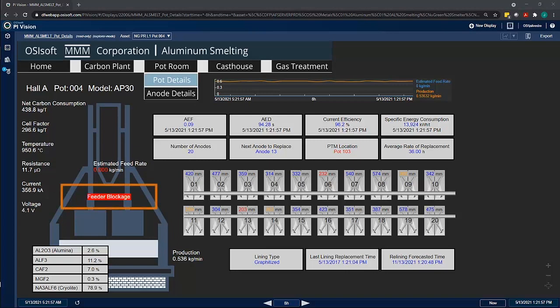The feeder blockage status does not come from a sensor or instrument, but it's rather inferred by using other sensor data and conditions available from the source systems. For example, the potential blockage of the feeder has been inferred by other data such as resistance, feed valve position, and beam activity.